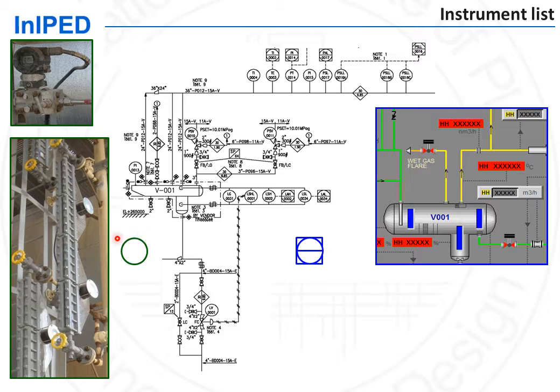This symbology is international. It is the International Society of Automation, ISA, symbology. So instruments with a circle are local instruments; instruments with a square frame are available on the operator display remotely in the control room.